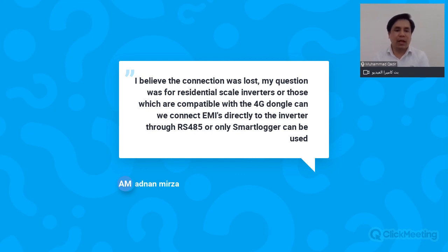Adnan Mirza is asking, I believe the connection was lost. My question was for residential scale inverters or those which are compatible with the 4G dongle. Can we connect EMIs directly to the inverter through RS485 or can a smart logger be used? As explained again, you will need a smart logger in whichever size of PV system or whichever size of inverter you are using from Huawei. So you must use a smart logger in order to communicate with the weather station or EMI. Normally, for a small PV system such as residential scenarios, you do not need to have a weather station.